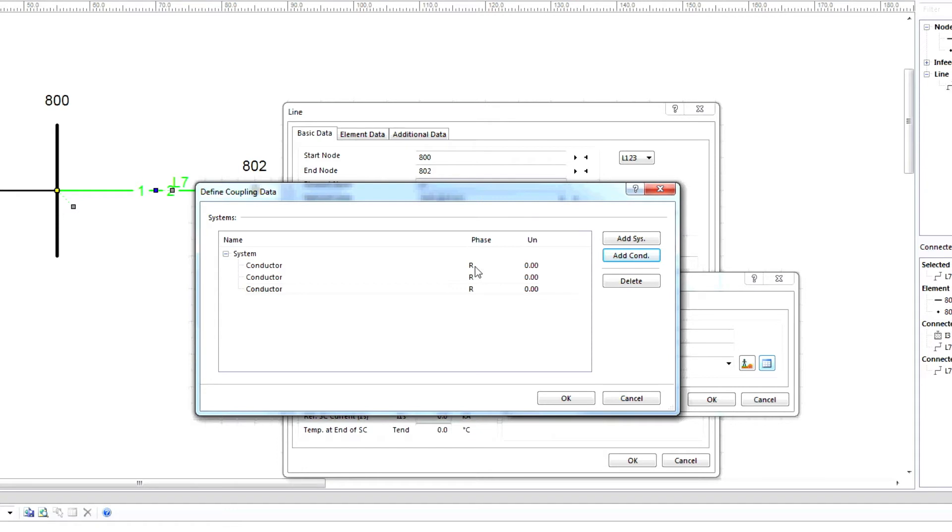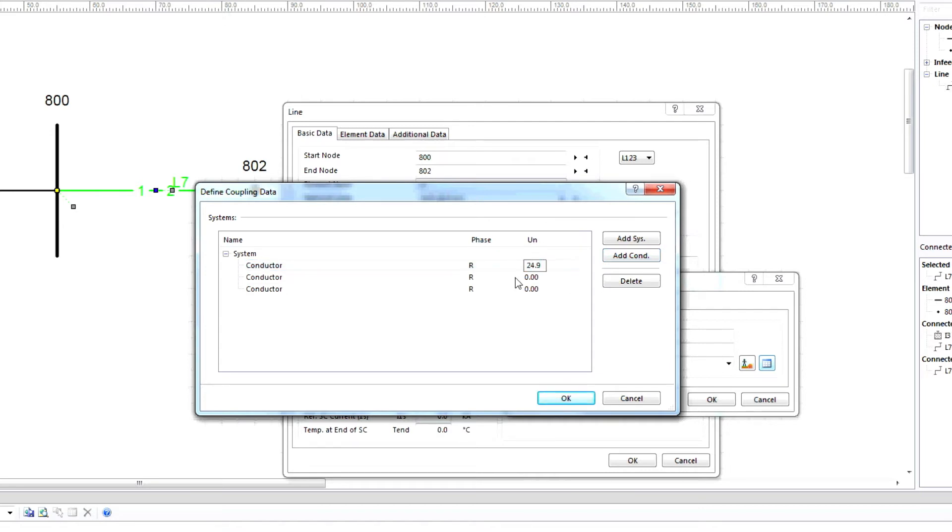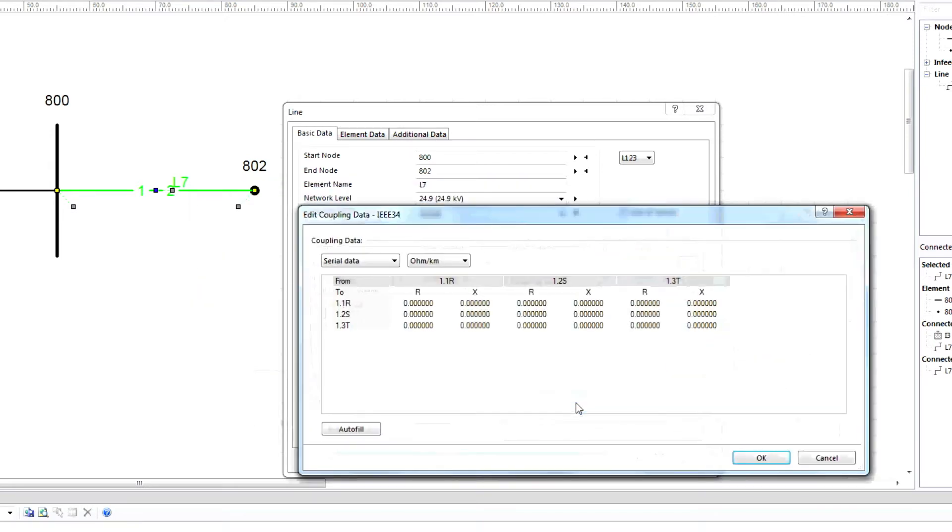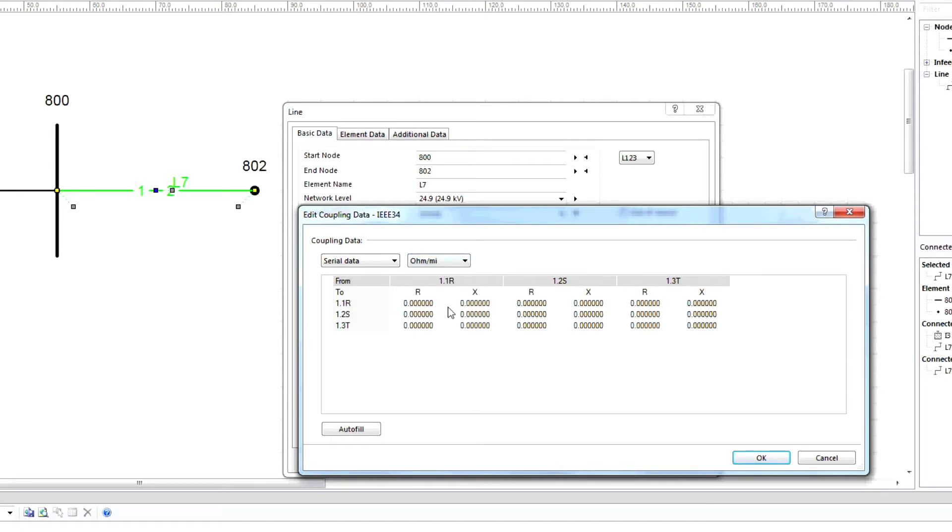Provide the phase and voltage information. Enter 24.9 as the voltage level of the system for each phase. Please note that RST is the phase naming that can also be L1, L2, L3. Next, enter the impedances provided by IEEE and then select the unit ohm per mile for serial data.